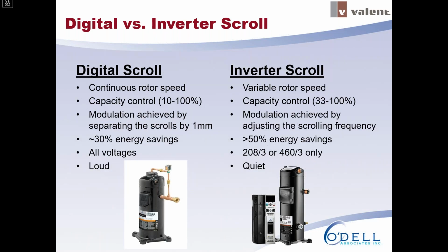Here's a side-by-side comparison of a digital scroll and an inverter scroll and the pros and cons. So like I said, the digital scroll has a continuous rotor speed, and an inverter scroll has a variable rotor speed. You get a little bit better turn down with a digital scroll compressor, down to 10% versus only down to 30% with an inverter scroll, but that's still pretty good. And again, modulation is achieved by that unloading, so the scrolls separate by about 1 millimeter. The inverter scroll, again, the modulation is achieved by adjusting that scrolling frequency.